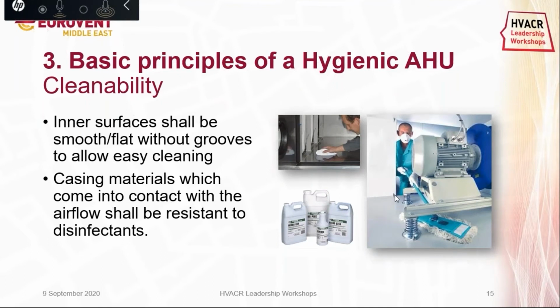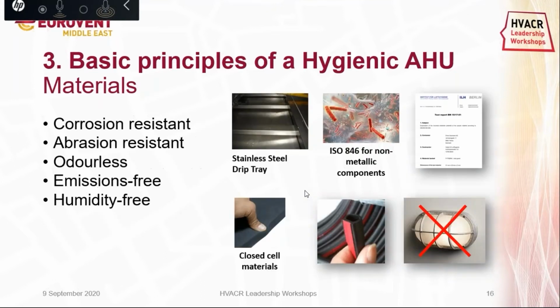Inner surfaces shall be smooth and flat without grooves to allow easy cleaning, and casing materials which come into contact with the airflow shall be resistant to disinfectants. Materials used in a hygienic air handling unit construction are extremely important when we talk about hygiene purposes. Non-metallic materials shall be tested and validated with respect to ISO 846 standard, which is the evaluation of the action of microorganisms on plastics.